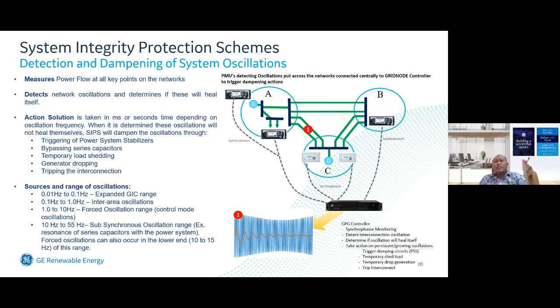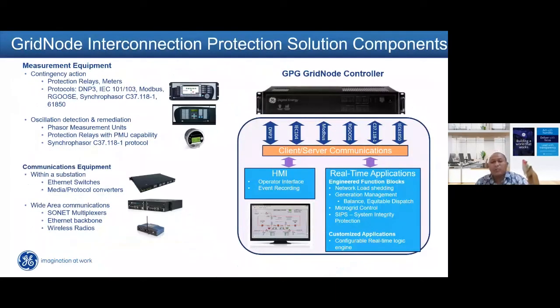So what are the components inside of this defense scheme or SIPS solution? What we have here, we can see at the right side, is the controller called GPG grid node, where GPG stands for GE Power Gateway. This controller will be connected with the devices scattered across the substations in the system. It can use protocols such as DNP3, IEC 104, Modbus, RGOOSE, C37, IEC 61850. And from this controller, it can be monitored or connected through the HMI for the operator interface as well as for event recording.